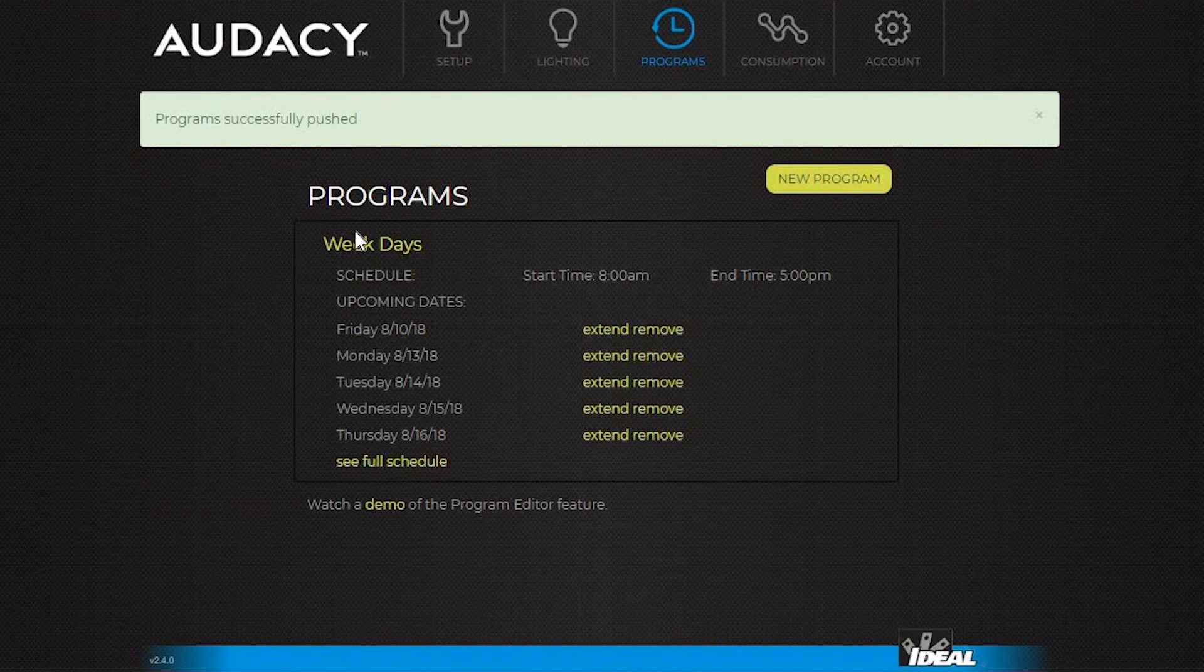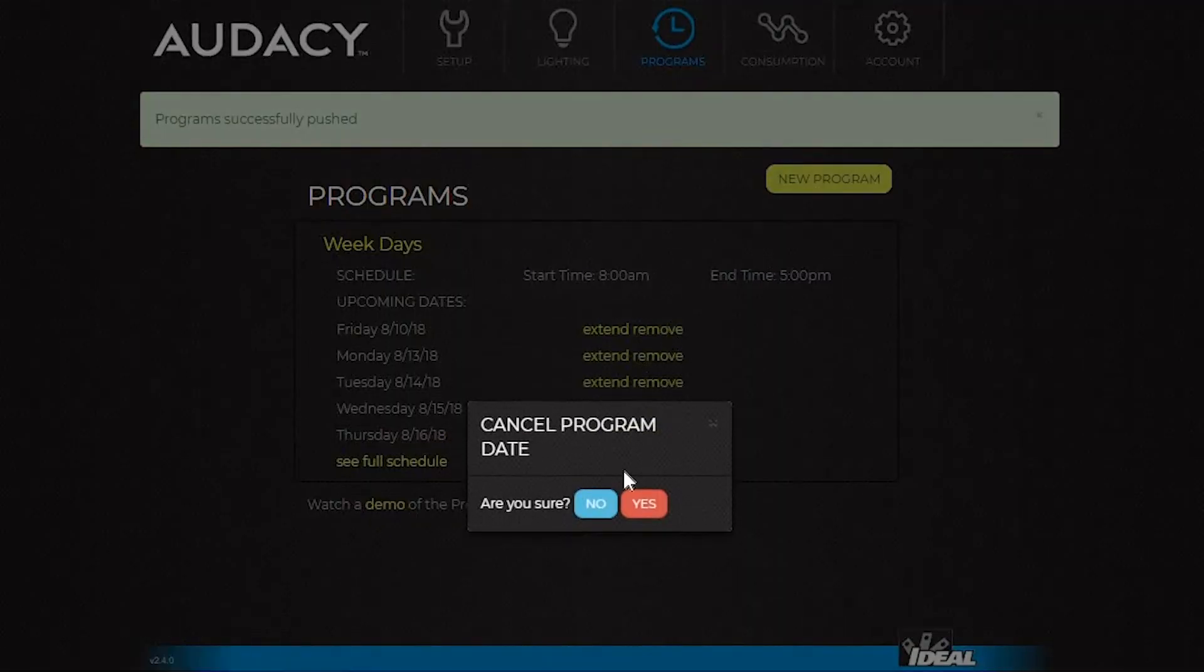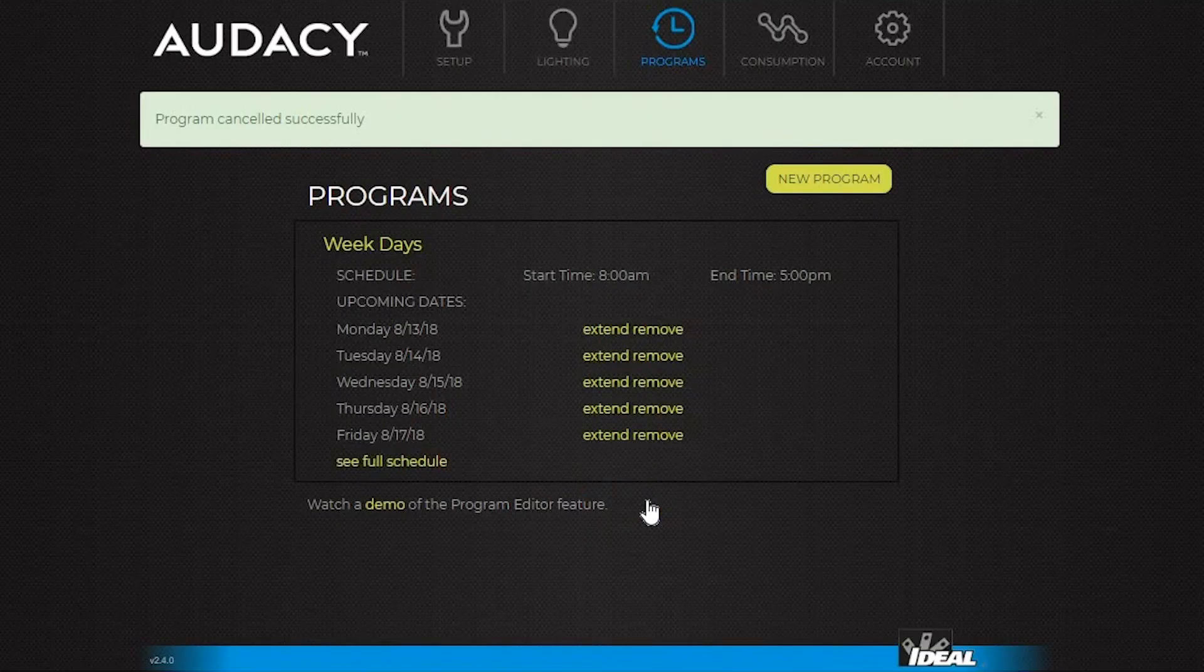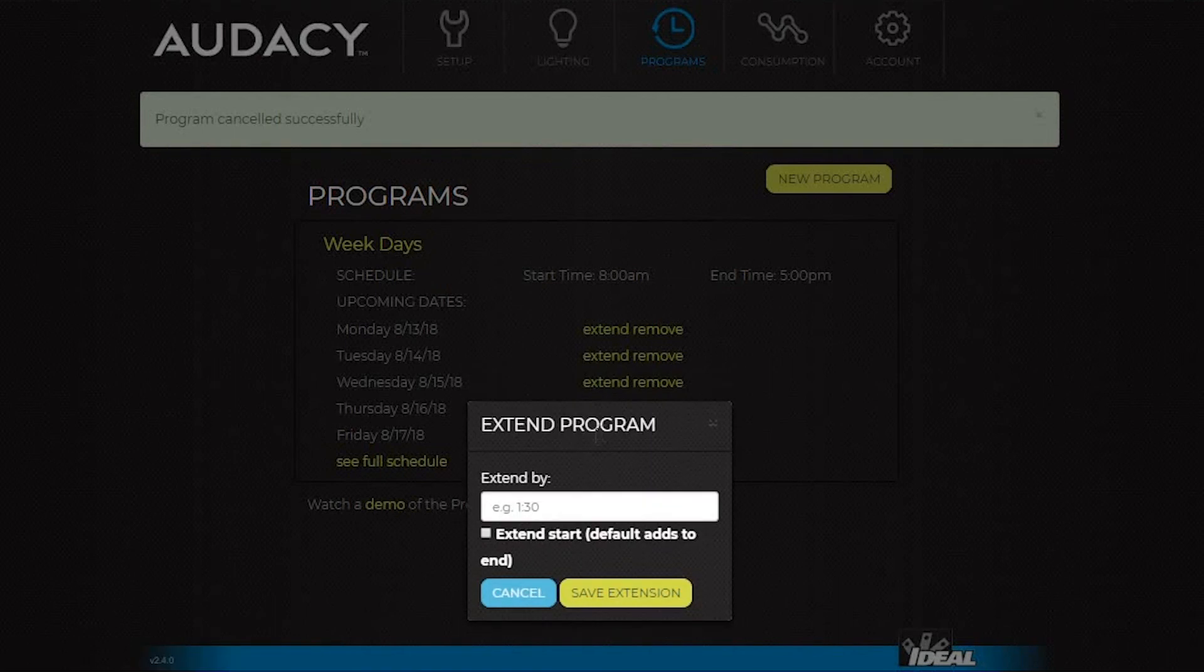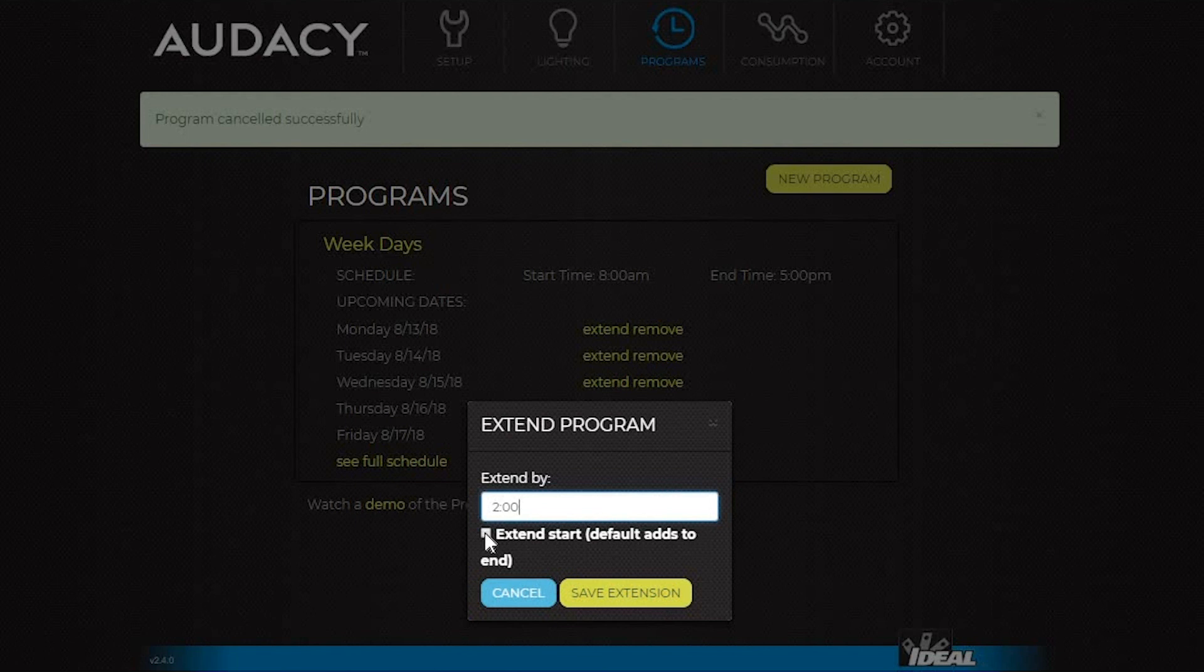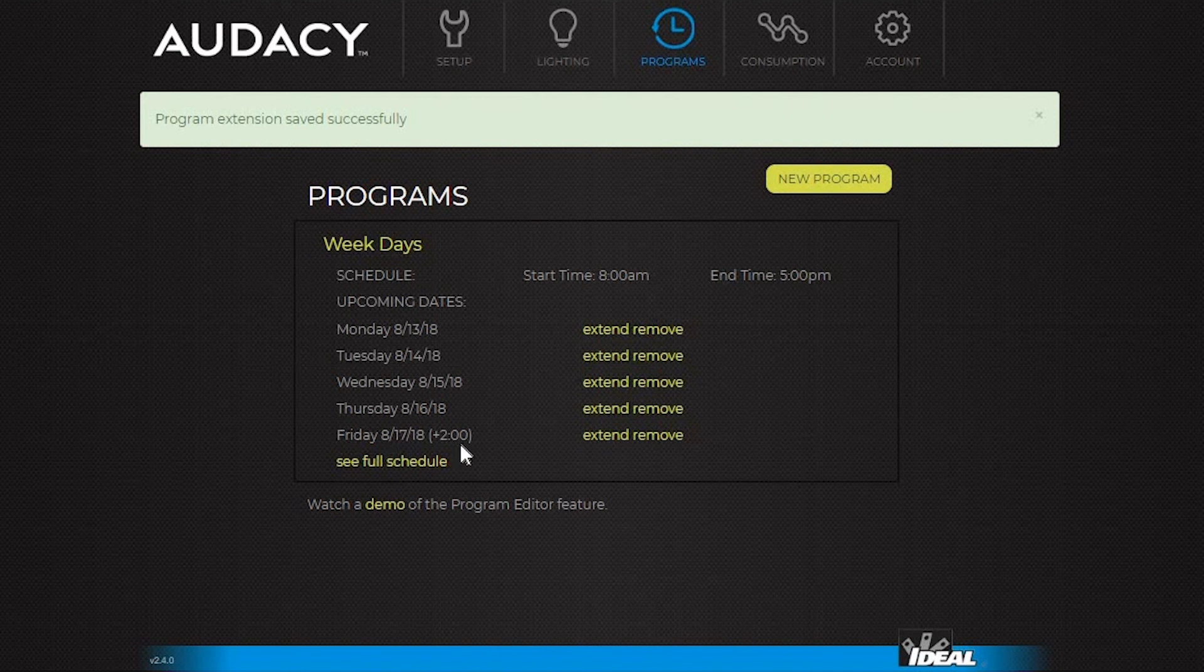Individual dates can also be removed from the screen. If Friday is a holiday, click Remove and hit Yes under Cancel Programs Date. Programs can also be extended on the screen. If people are working late on Friday, the program can be extended by typing in the desired length of time in hours and minutes. Or if people are coming in early, select Extend Start and then click Save Extension. Now the program shows plus 2 on Friday, meaning the lights will stay on two hours later than they normally would.